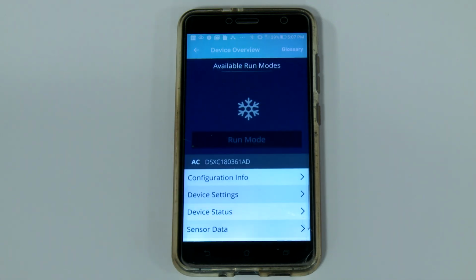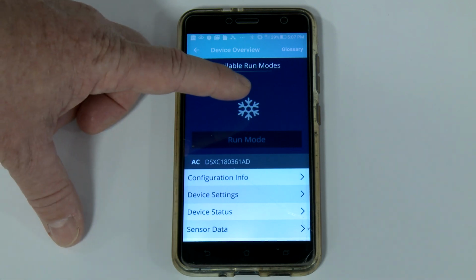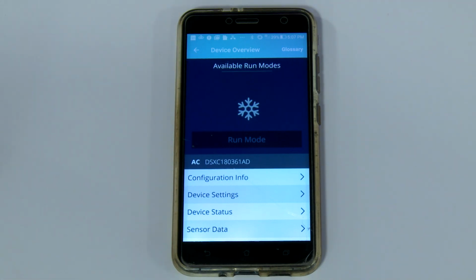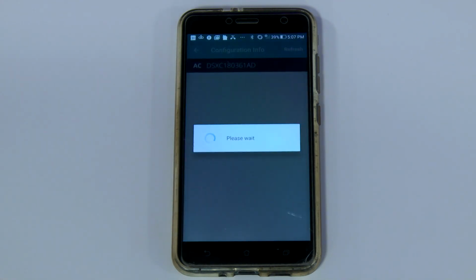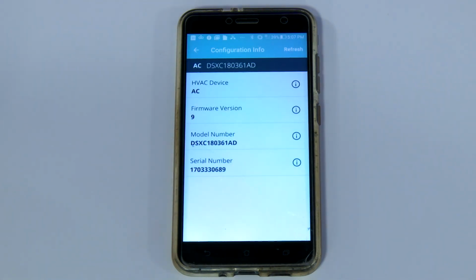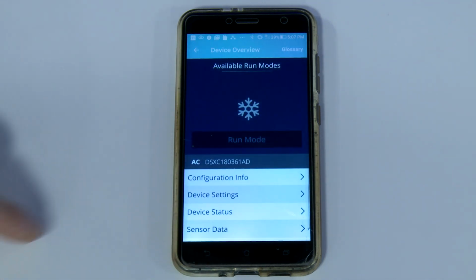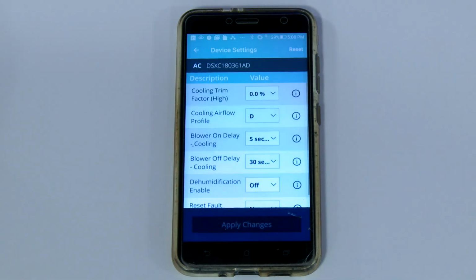Now let's go back to the main menu and look at the air conditioner that is connected to this system. A run test can be completed on this specific equipment by selecting the snowflake displayed. In the configuration menu, much like was available when viewing the gas furnace, it will display specific information about the equipment, such as the model number and the serial number of the equipment. When you open the device settings, you'll find that the outdoor unit has an assortment of available adjustments. Some of those apply indirectly to the indoor equipment also.